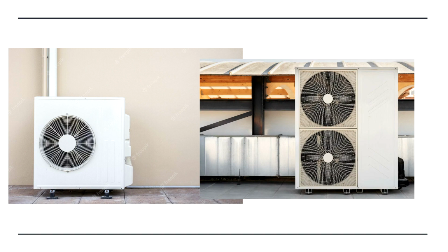Okay, the image on the right is another one. This one has a larger condenser coil, but requires 2 fans to operate. So the one on the left is somewhere in the neighborhood of 3 to 4 tons, and the one on the right is 5 to 6 tons. Okay, and the ton I'll explain in a little bit, but just real quick, it's how we measure the heat capacity of refrigeration systems.